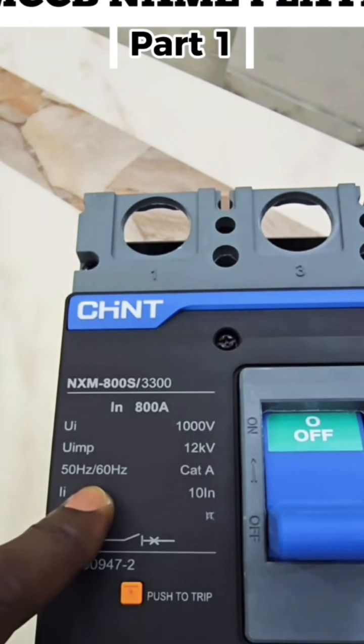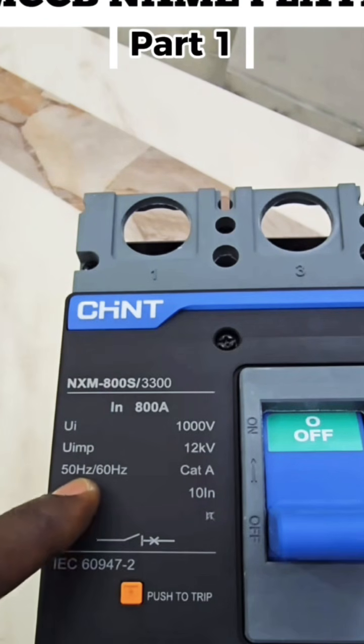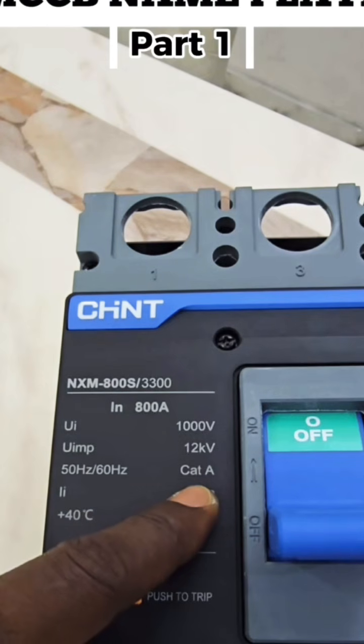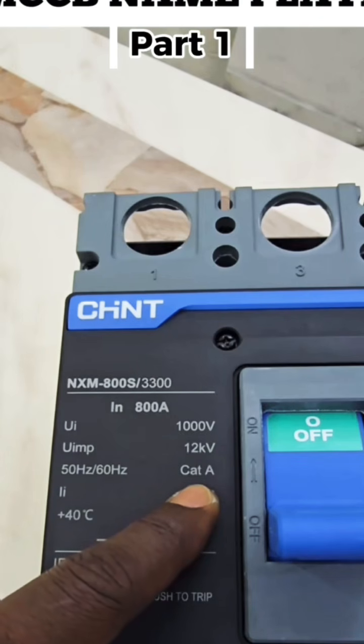50 Hz, 60 Hz means this circuit breaker can work under both 50 Hz and 60 Hz conditions. Cat A is the category of this circuit breaker. Category A circuit breakers are just basic circuit breakers which trip without any form of delay. There is no form of discrimination, and it doesn't have any settings that the operator can apply to it.